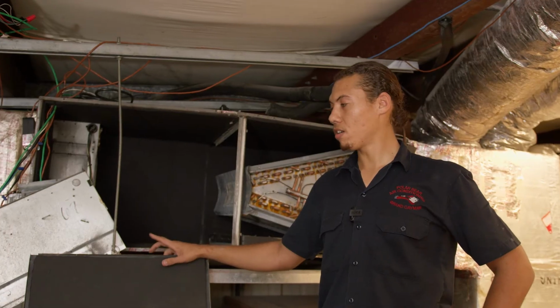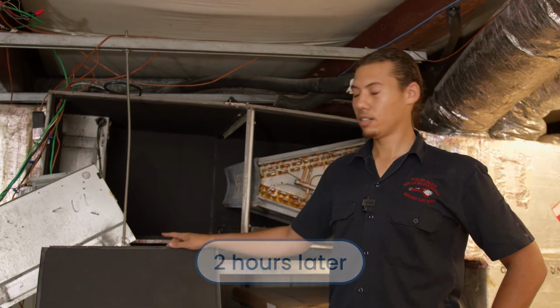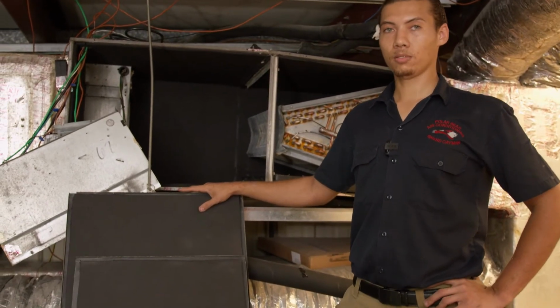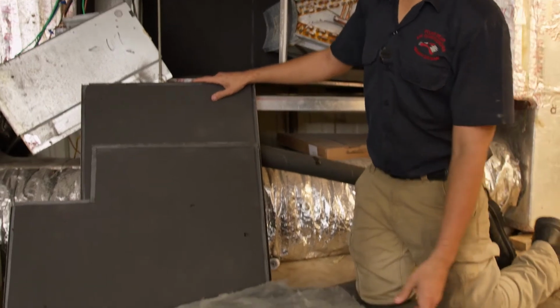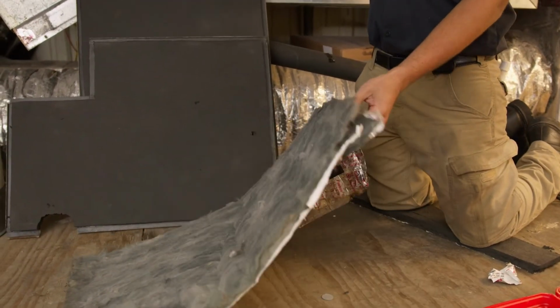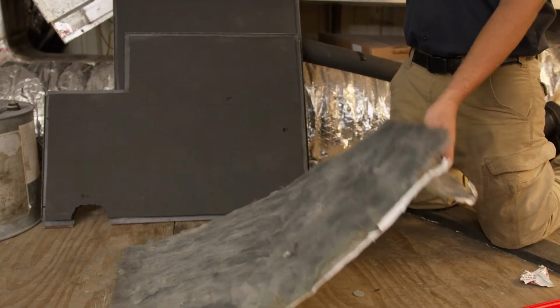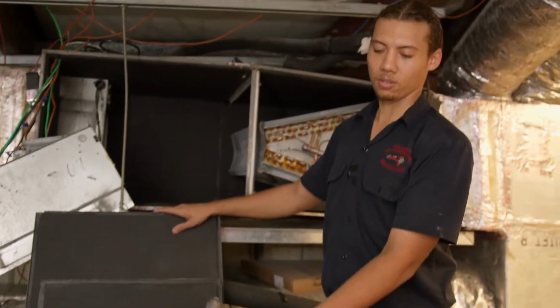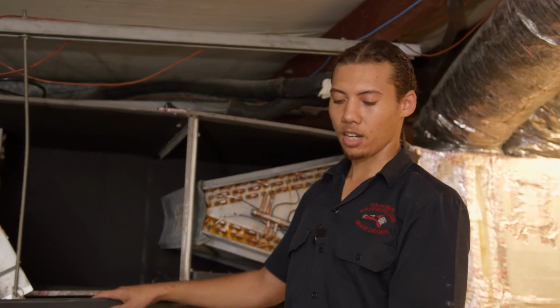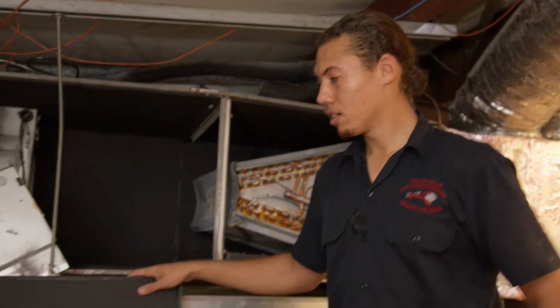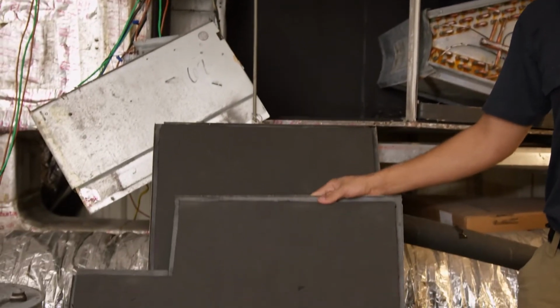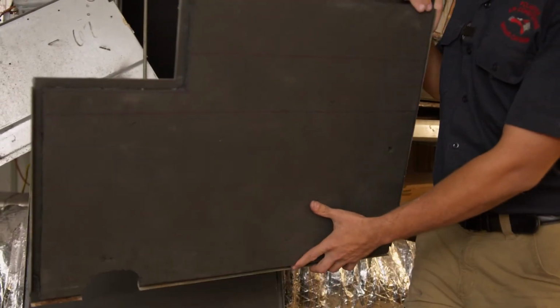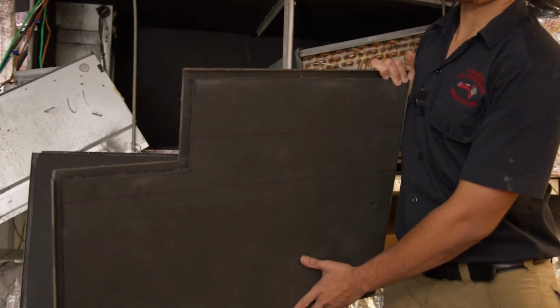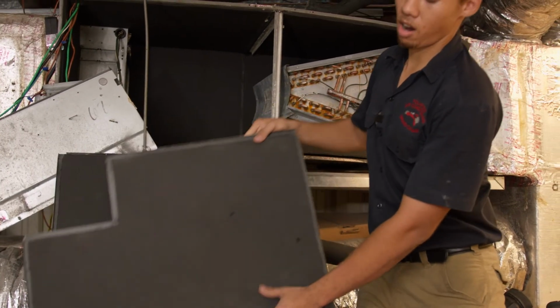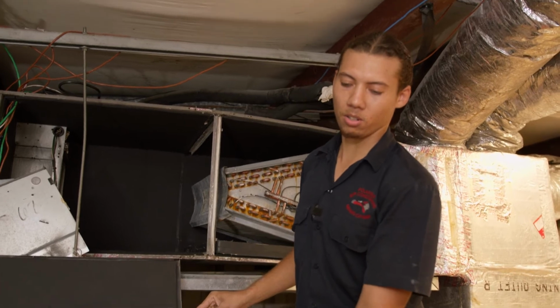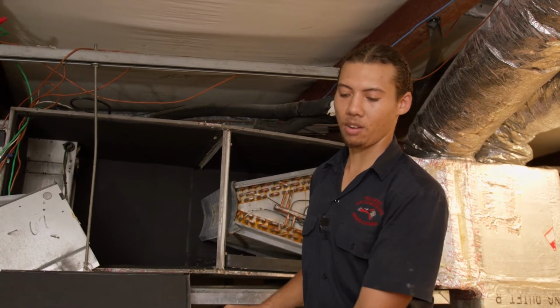So now we installed all the new insulation into the air handler, including the door panels for the unit. You can see the old insulation is quite deteriorated and probably been wet for quite some time, turning a blackish color throughout. Because it was condensating, it clearly wasn't doing its job anymore. So the brand new insulation, as you can see, is much thicker and made of a material that is not going to get wet and not going to harbor any biological growth like a standard fiberglass one would.